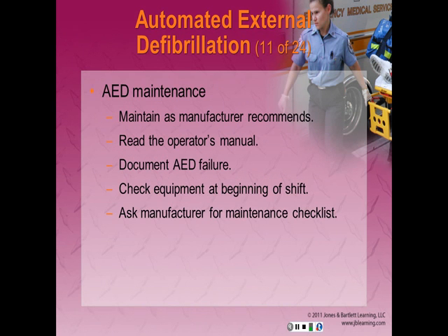AED maintenance is important. Become familiar with the maintenance procedures required for the brand of AED that your service uses. Read the operator's manual. Document AED failure, which will aid communication with an EMS administrator, the medical director, the media, or a patient's attorney. Make sure the batteries are properly maintained and check your equipment, including your AED, at the beginning of each shift.